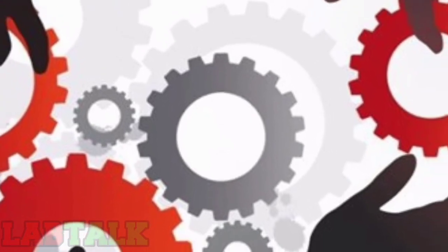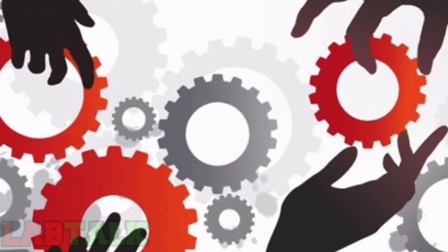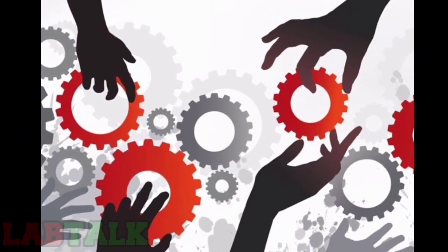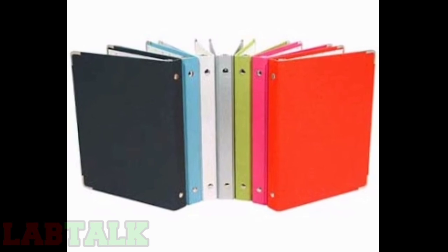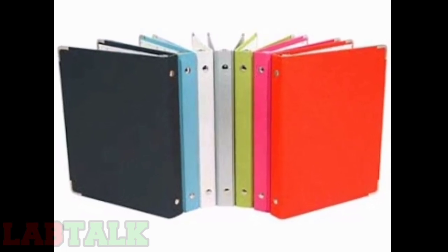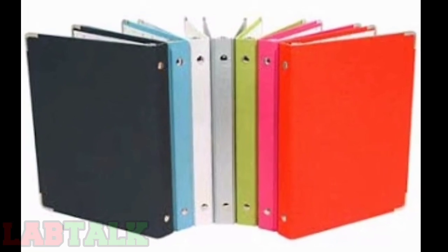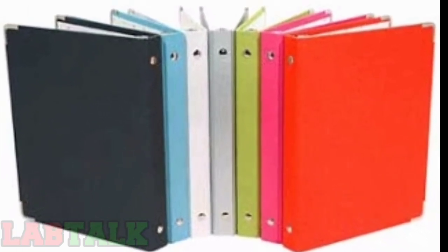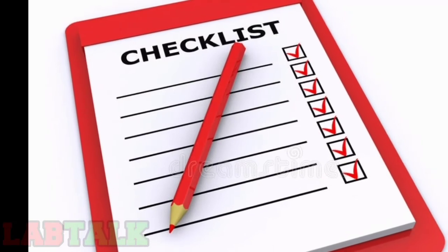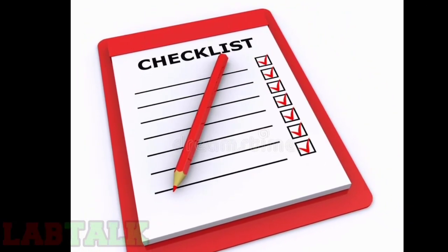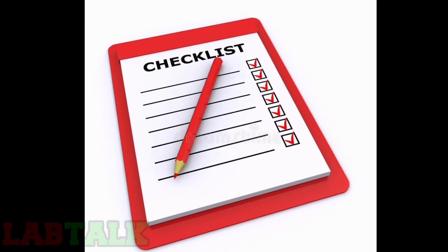All these records should be maintained and shall be readily available for the lifespan of the equipment or longer, as specified in the laboratory's control of records procedure. A list of all applicable standard operating procedures and other system documents relevant to the equipment should be maintained. And finally, confirm that all these records are available at the point of use and approved by the Quality Management System Department.